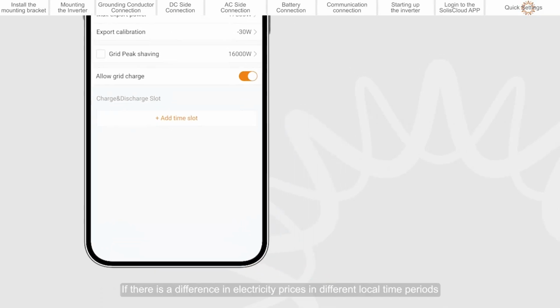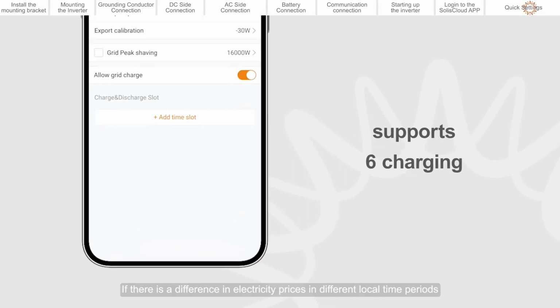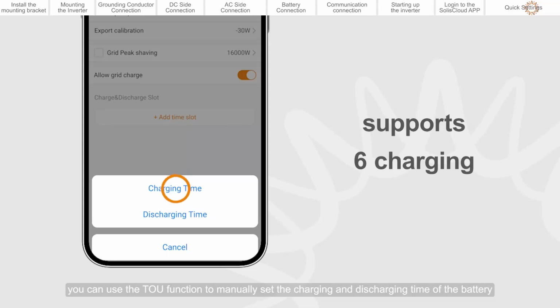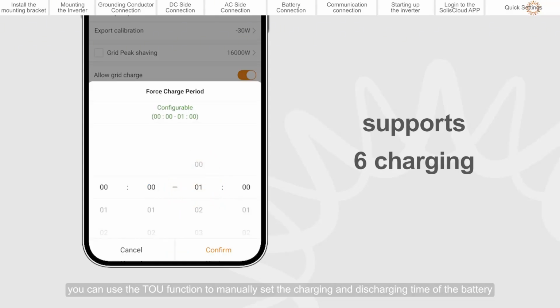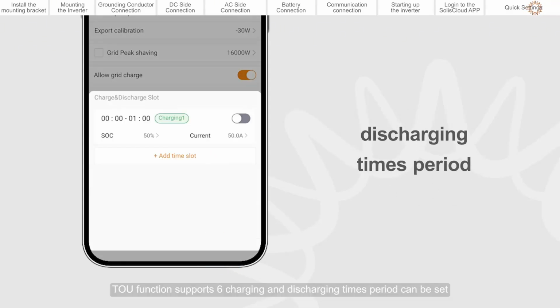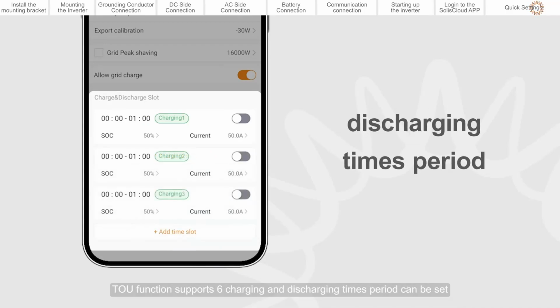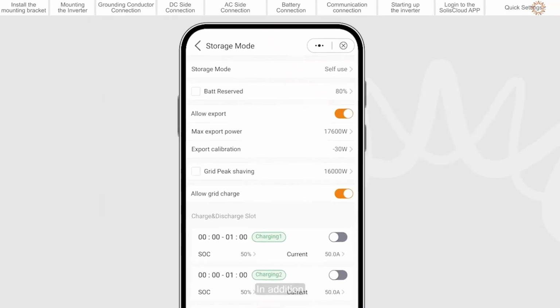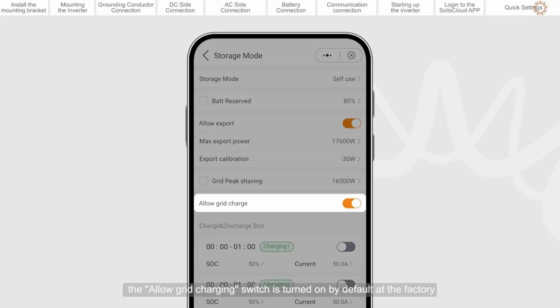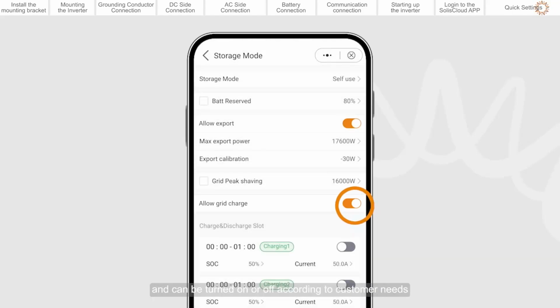If there is a difference in electricity prices in different local time periods, you can use the TOU function to manually set the charging and discharging time of the battery. The TOU function supports 6 charging and discharging time periods that can be set. In addition, the allow grid charging switch is turned on by default at the factory and can be turned on or off according to customer needs.